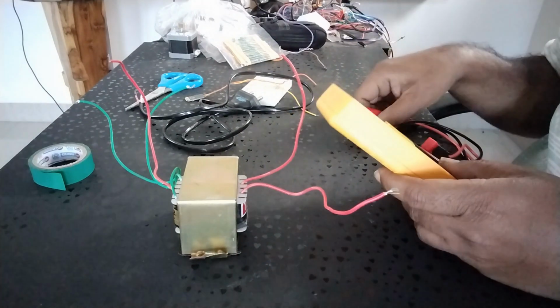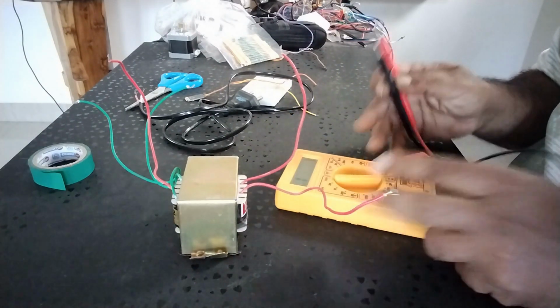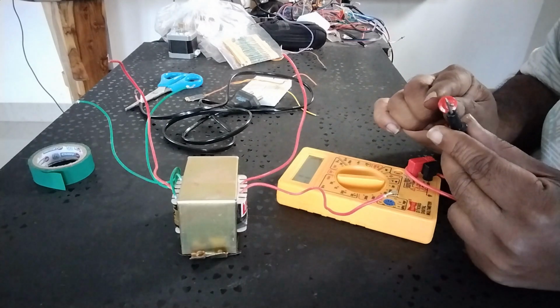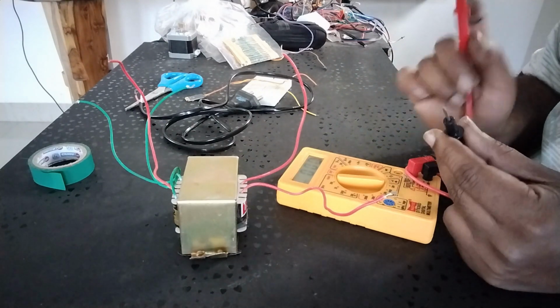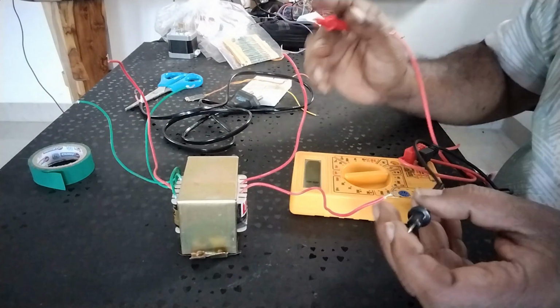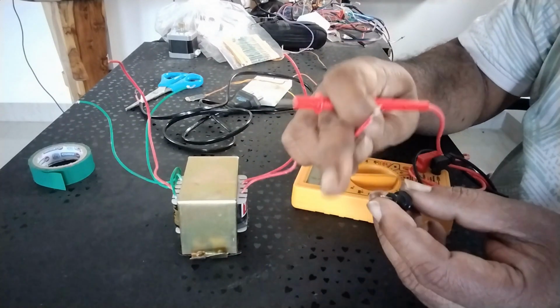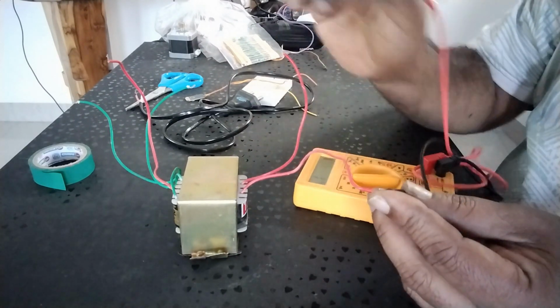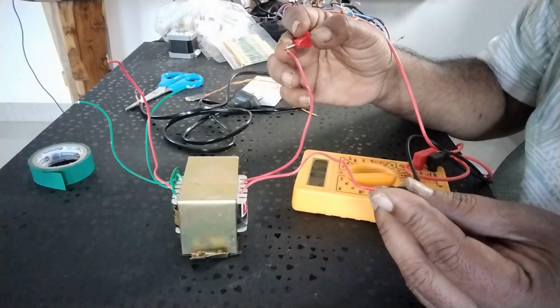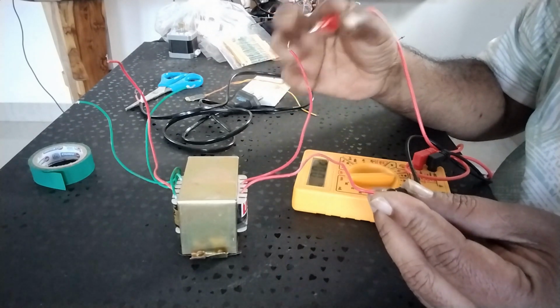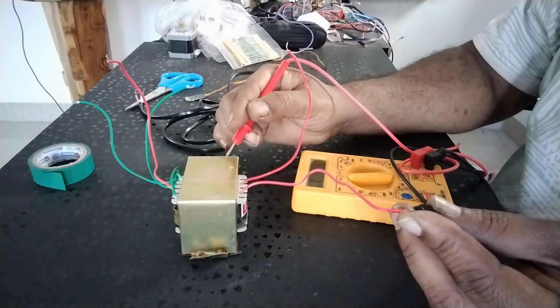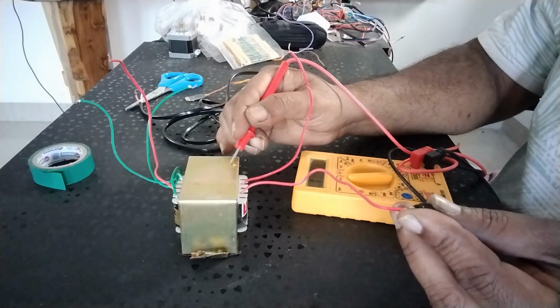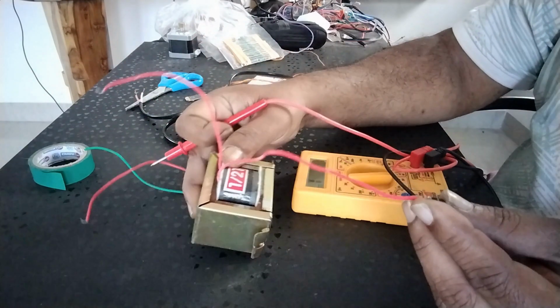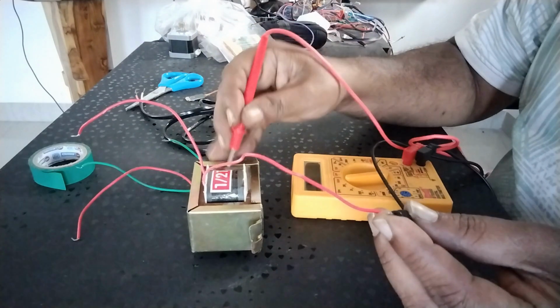Check continuity of primary windings. Set your multimeter to continuity test mode, often represented by a sound wave or diode symbol. Connect the two probes of the multimeter to the two terminals of the primary winding. If the multimeter produces a continuous beep, it indicates that the primary winding is intact, with no breaks. This means it is safe to connect to an AC power source. If there is no beep, the primary winding is broken, and the transformer cannot function properly.